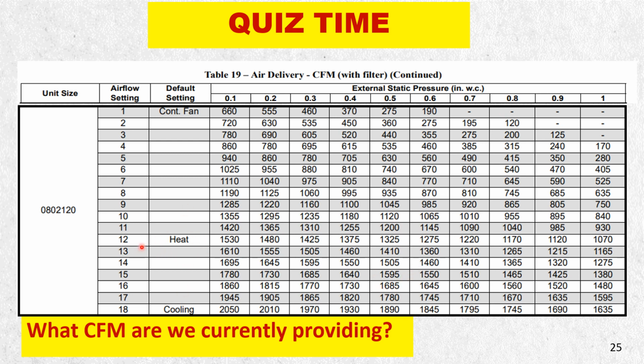This is why, just because I set it in a house, and let's say I'm in heat mode, and I take this 2000 unit, this 2000 CFM, because let's say I need 1600 CFM, and I'm using it like a 4-ton, and in heat mode, then if I look at my static pressure, which they want you to be right in this area here, but let's say you're in 0.70 to 0.80, where it says most of where the houses are set, look how many CFMs you're going to be losing.